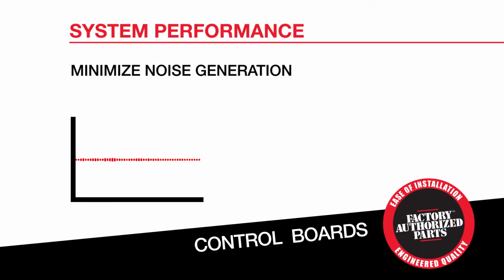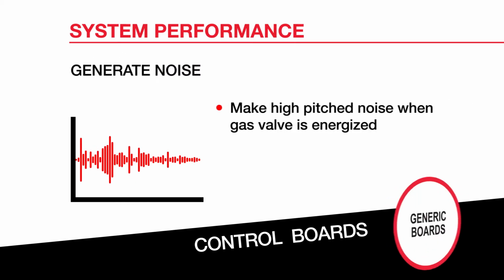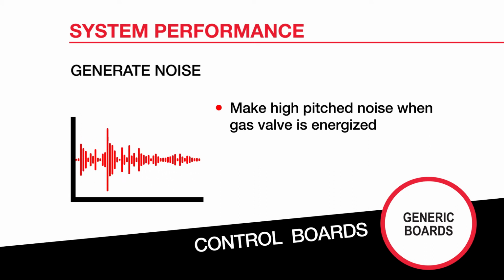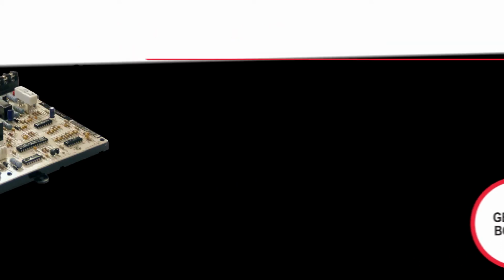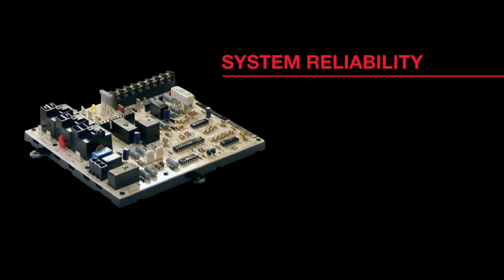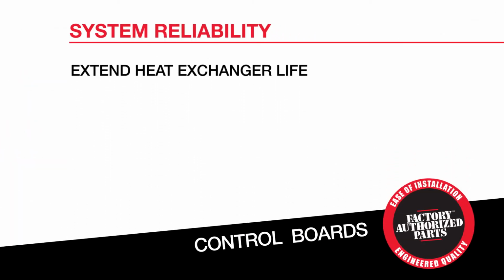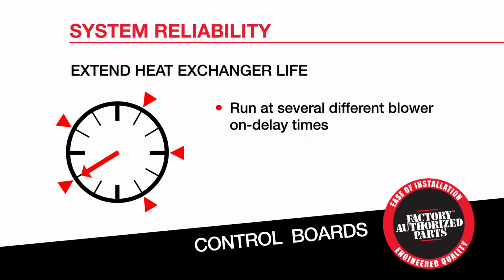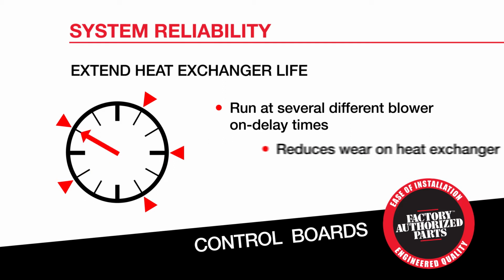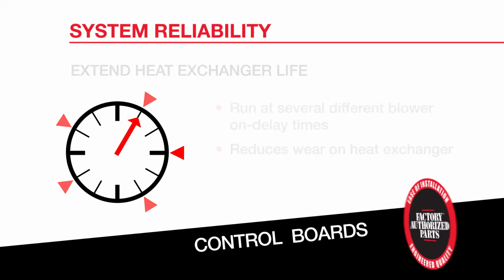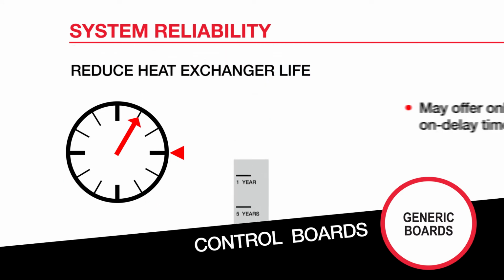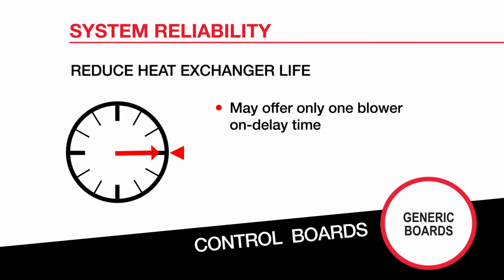Factory authorized parts boards also minimize noise generation. They're designed for quiet operation. Some generic boards make a noticeable high-pitched noise whenever the gas valve is energized. When you choose factory authorized parts control boards, you'll also improve the reliability of the system. Factory authorized parts boards can significantly extend heat exchanger life because they're designed to run at several different blower on delay times, depending on the product type. Use of the correct blower on delay reduces wear on the heat exchanger. Some generic boards can reduce the life of the heat exchanger because they may offer only one blower on delay time.